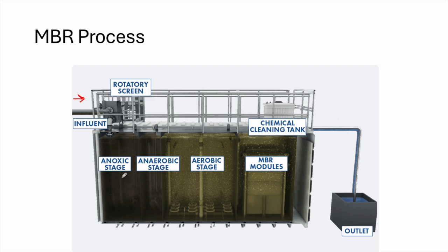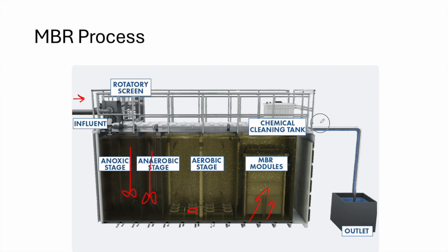Then the wastewater undergoes an anoxic stage using a mixer with no aeration — then anaerobic stage using mixers. Next, the wastewater undergoes an aerobic stage with diffusion of air through round air bubble diffusers. Note that there is no media here — just the water placed in aerobic condition — and finally this wastewater is filtered through MBR modules, also under aerobic conditions.